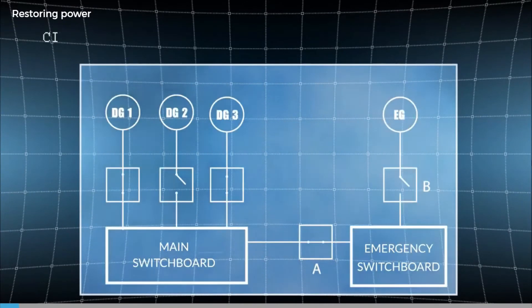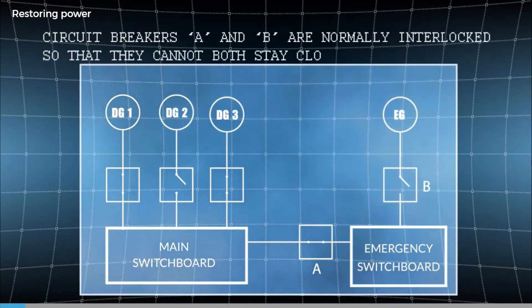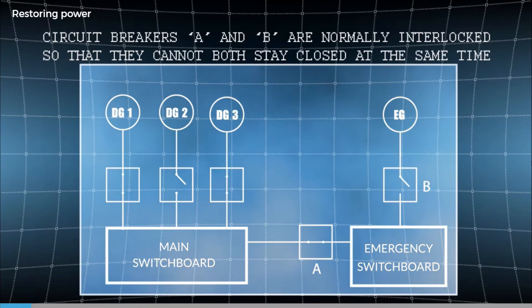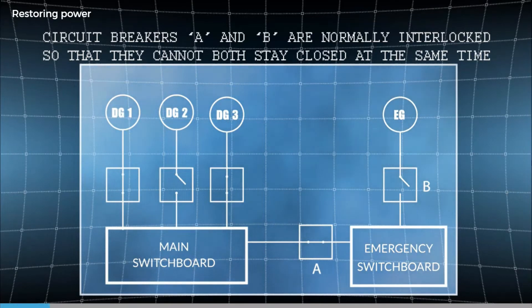We need to keep in mind that on most, but not all, ships, we can't run the main and emergency generators in parallel. We can often synchronise them, but there are usually two circuit breakers, arranged so that only one of them can be closed at any given time.